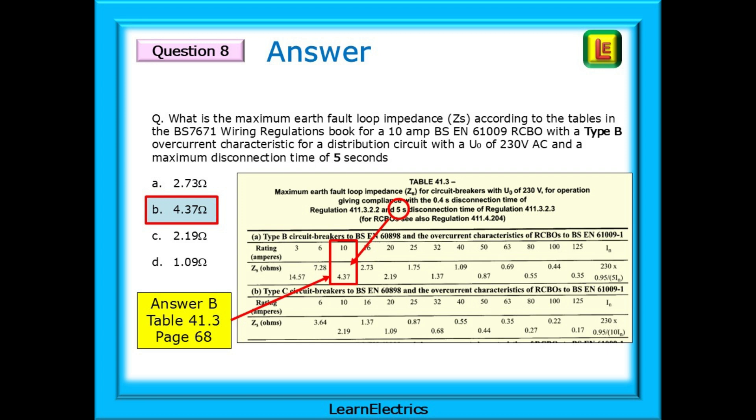So, look in the index on page 583 for disconnection times, final circuits and you will be directed to table 41.1. And since the question mentions tables, just turn a page or two to find table 41.3 for circuit breakers and RCBOs.